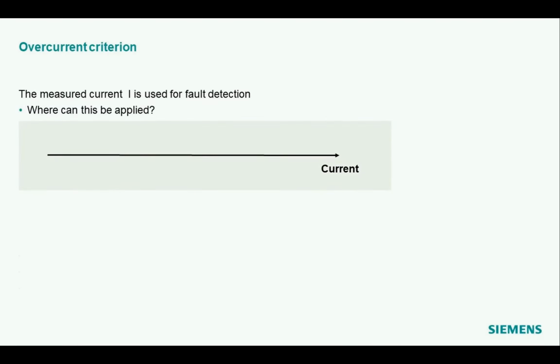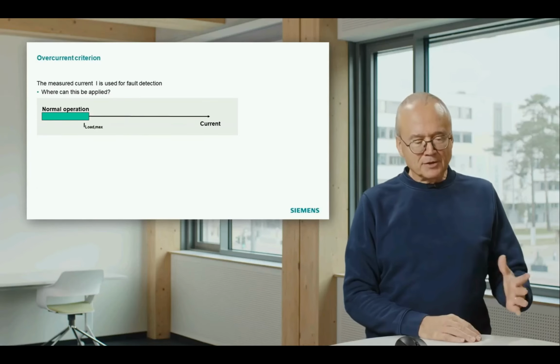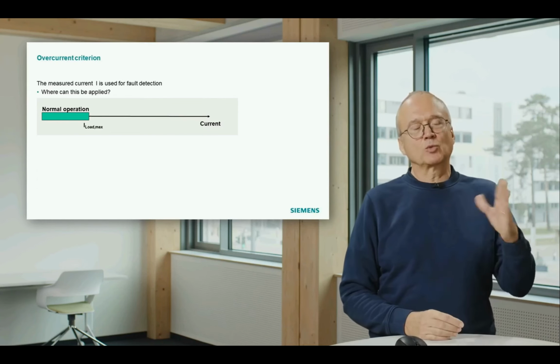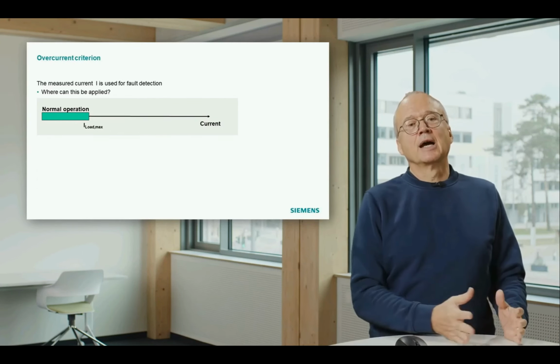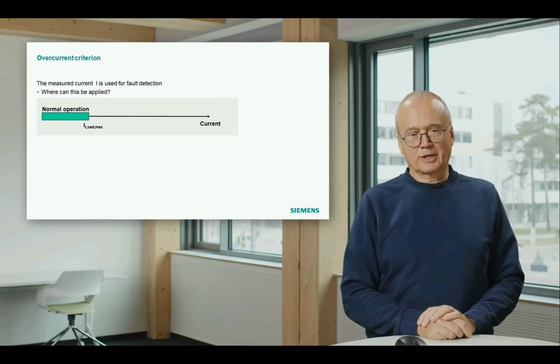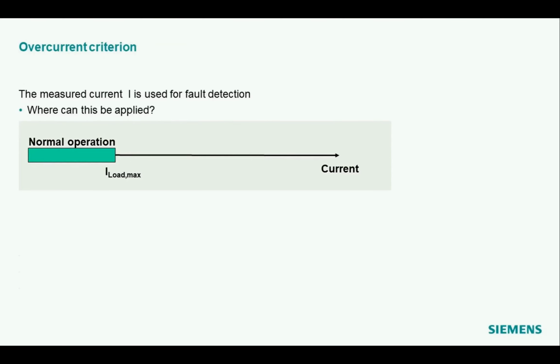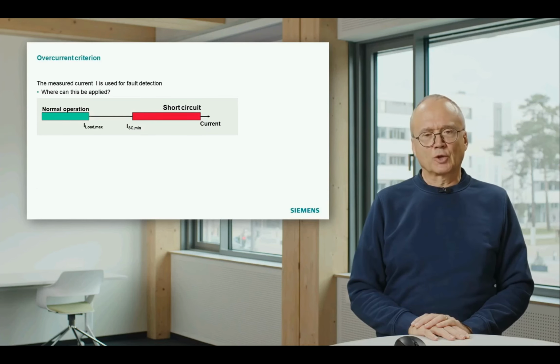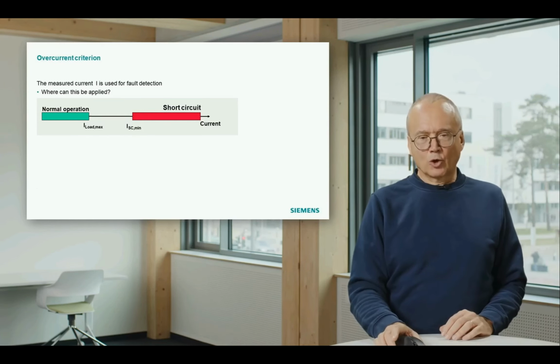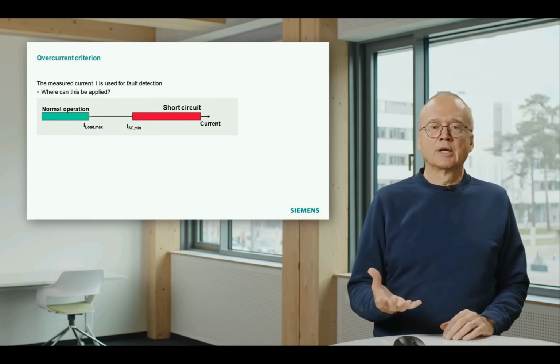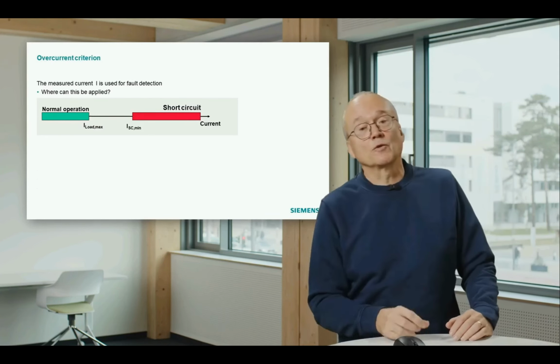Imagine we have a certain range of currents, and what I indicate here in green is the normal operation. That means in normal operation we measure a current between 0 on the left-hand side up to a maximum load current. And then we have a range of short circuit currents. Typically, when you engineer your substation, you calculate the maximum short circuit current which may occur.